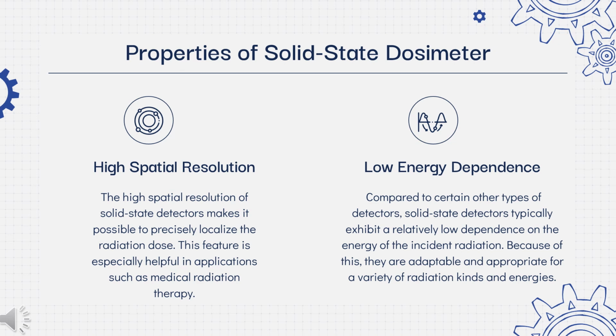Low energy dependence. The response of a dosimetry system is generally a function of radiation beam quality, which means energy. But compared to certain other types of detectors, solid-state detectors typically exhibit a relatively low dependence on the energy of the incident radiation. Because of this, they are adaptable and appropriate for a variety of radiation kinds and energies. In general, the variation due to the energy dependence should be corrected for.